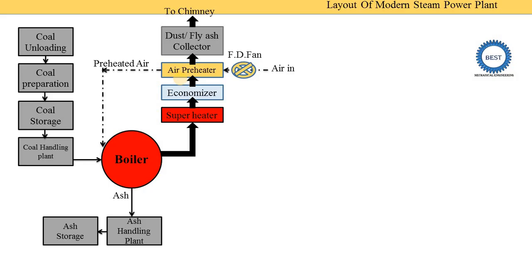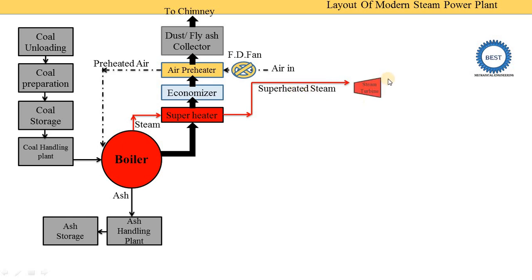Now the third circuit is the water and steam circuit. Similar to how we drink water and remove it from the body, the steam power plant circulates water and steam. We start from the steam side for easier understanding. In the boiler, water is supplied from the economizer. Saturated steam from the boiler is supplied to the superheater. In the superheater, the temperature of the steam is further increased above the saturation temperature. This superheated steam is then supplied to the turbine.